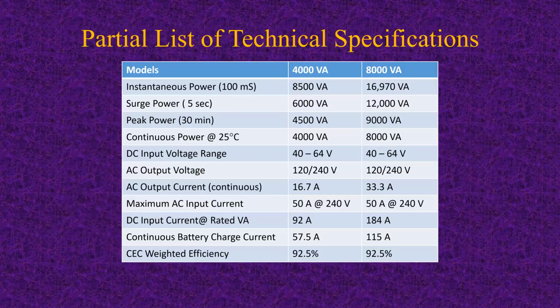All right, so here are two models that were available a while ago, and you can still buy them now if you want to do things the older way. Both of these, I think, have been incorporated into some of the newer systems that have it all in one box. Here's a 4,000 volt ampere system that has a continuous power rating of 4,000 volt amps, although it will kick out more than that if you want to start a motor when it's running independently of the grid. And then its big brother is twice as big. DC input voltage range on these happens to be 40 to 64. Their output is 120/240, and you can unbalance that up to about 80%. The AC output current is obviously twice as much for the bigger one.